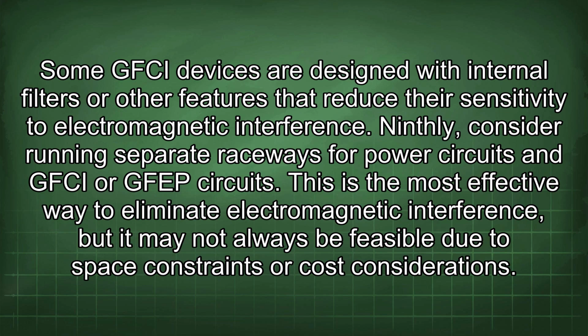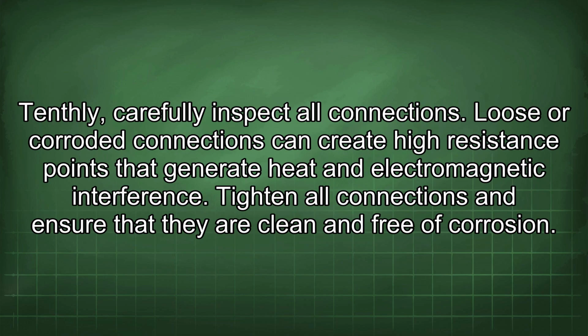Ninthly, consider running separate raceways for power circuits and GFCI or GFEP circuits. This is the most effective way to eliminate electromagnetic interference, but it may not always be feasible due to space constraints or cost considerations. Tenthly, carefully inspect all connections. Loose or corroded connections can create high resistance points that generate heat and electromagnetic interference. Tighten all connections and ensure that they are clean and free of corrosion.